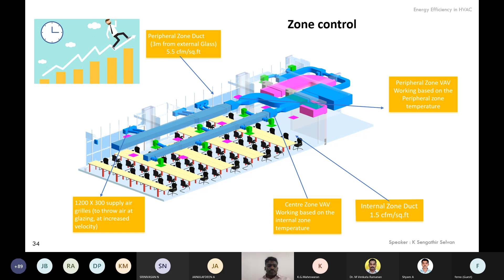We have discussed zone control and 30% additional fresh air, and ECM 11 means increased temperature - instead of 23 degrees, setting it to 25 degrees. You can see the power consumption reduced from 81 lakhs to 77 lakhs, a huge reduction mainly because of increasing the room temperature to 24-25 degrees. Here energy consumption increases mainly because we bring in additional 30% fresh air, but that is required for human health.